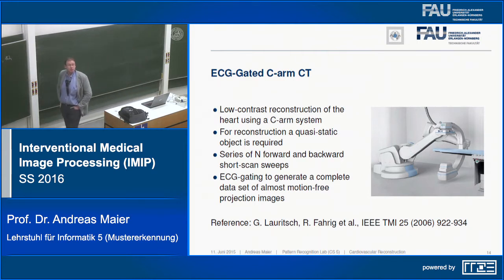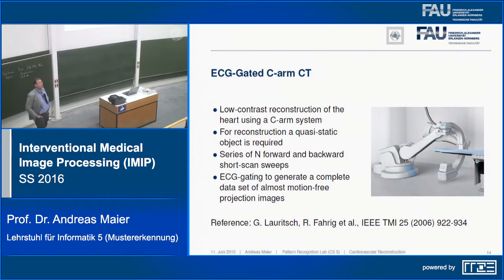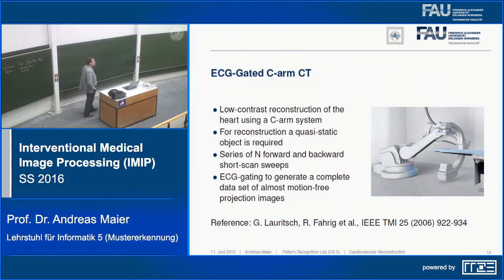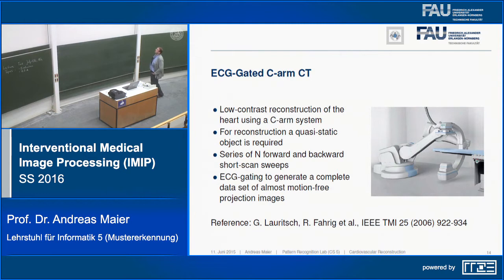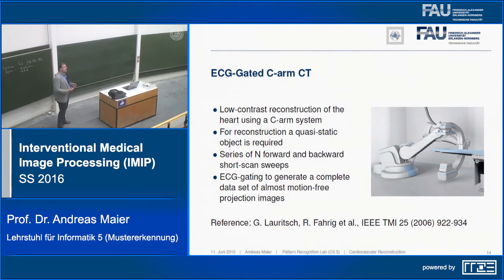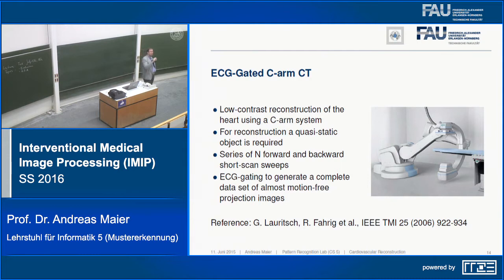We were talking about ECG-gated reconstruction and motion-compensated reconstruction. Last lecture we learned that all of the reconstruction theory is essentially assuming that we have a static object. Unfortunately, patients are not static objects. One idea from 2006 is that you virtually freeze the heart — reconstructing by taking projections from different angles but only using those acquired in the same heart phase, then putting them together to reconstruct.